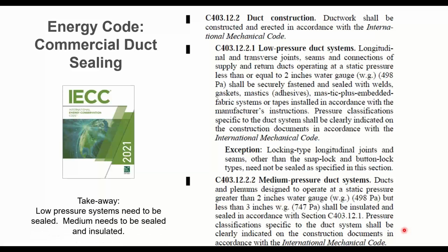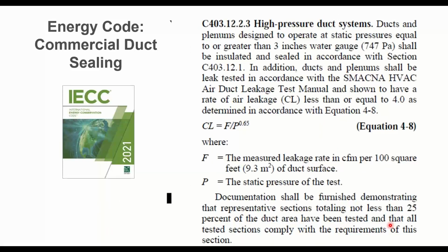So the takeaway on that is low pressure systems, you got to seal it. Medium pressure, you have to seal it and insulate it. I should have mentioned that as well. And then when you get to high pressure systems, which is 3 inches and up, which is not a lot of systems these days, you not only have to seal it, but then you have to leak test it to prove you did a good job. Basically, we don't trust you. Prove it, you did a good job.